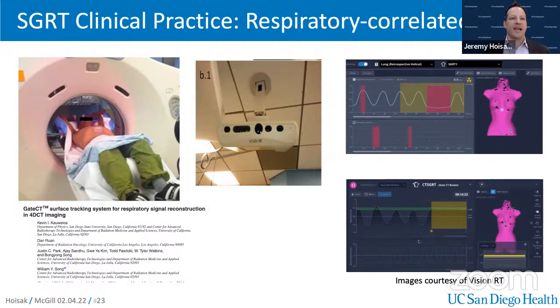But they did find it had several advantages when you use a Vision RT system or a surface SGRT system for the respiratory signal. We're less dependent on where this RPM block is placed, which can vary the amplitude of the respiration signal you get. And by having a more robust correlation or reproducible amplitude of the signal, we can have fewer artifacts in the CT scan from how we reconstructed that 4D CT. And this again translates into more reproducible breath tracking at the treatment machine.